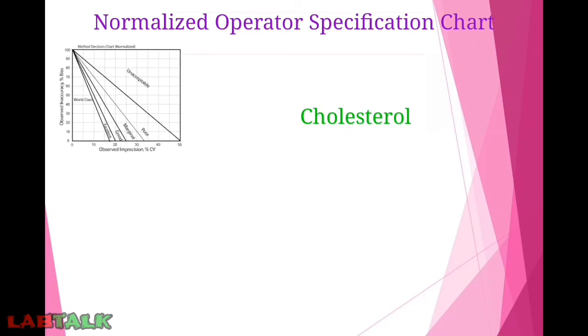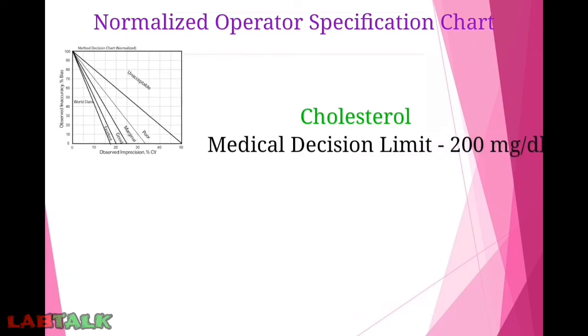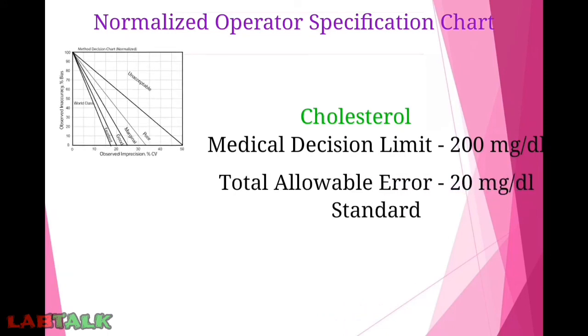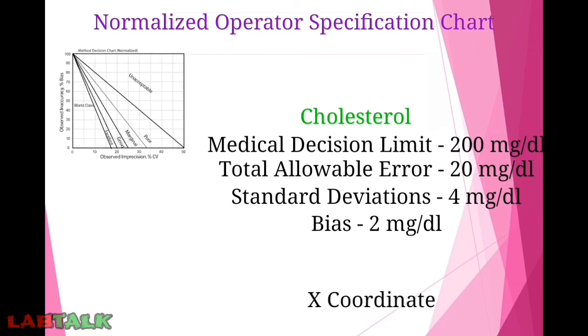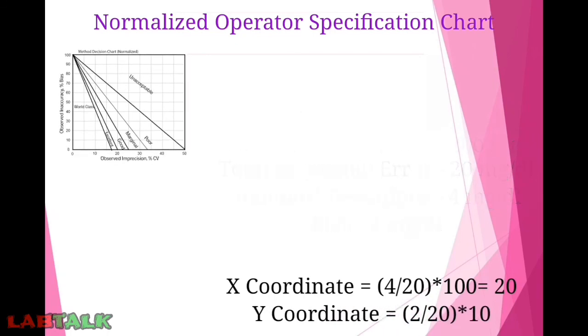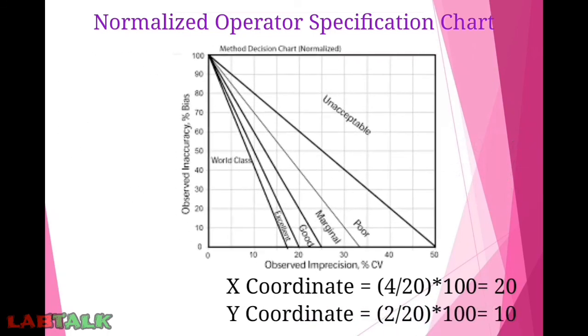Using the cholesterol example with a medical decision limit of 200 mg/dL, total allowable error of 20 mg/dL, standard deviation of 4 mg/dL, and bias of 2 mg/dL: the x-coordinate = (4 / 20) × 100 = 20, and the y-coordinate = (2 / 20) × 100 = 10. So the operating point coordinates are (20, 10).